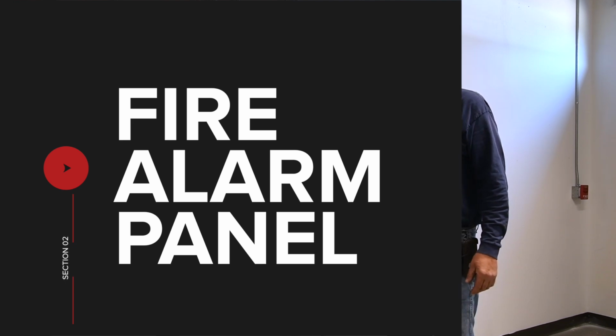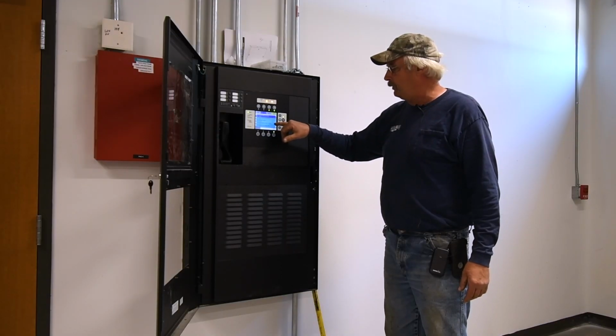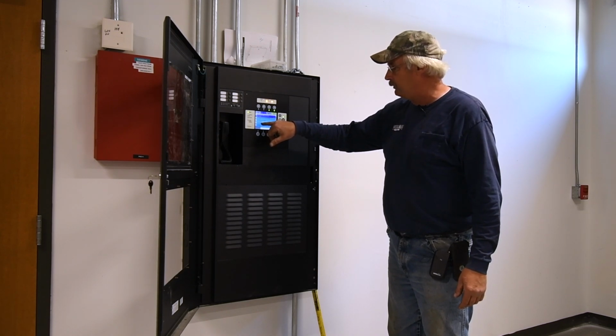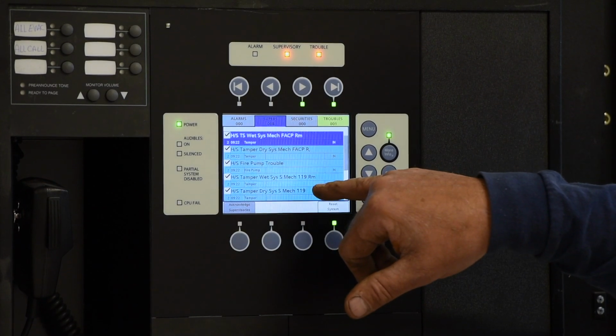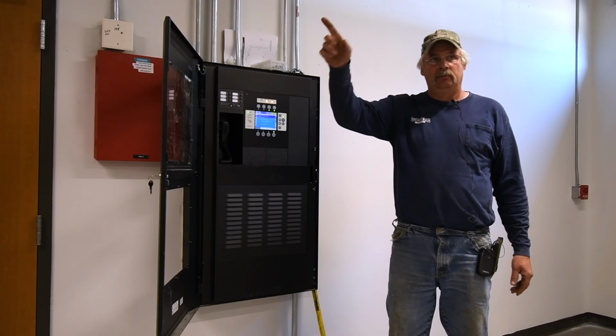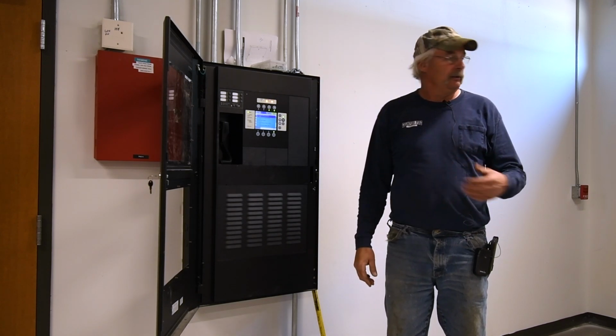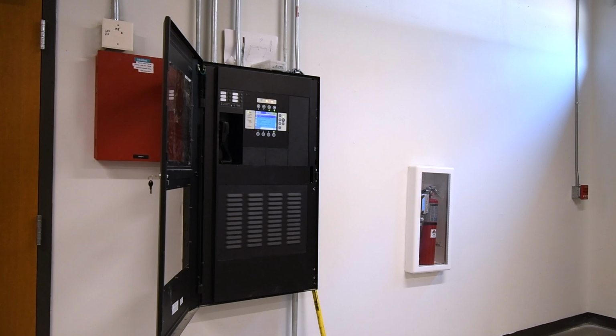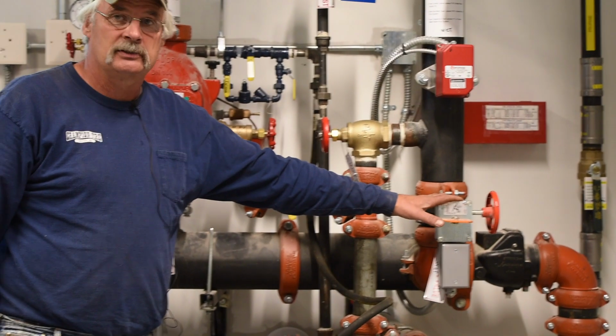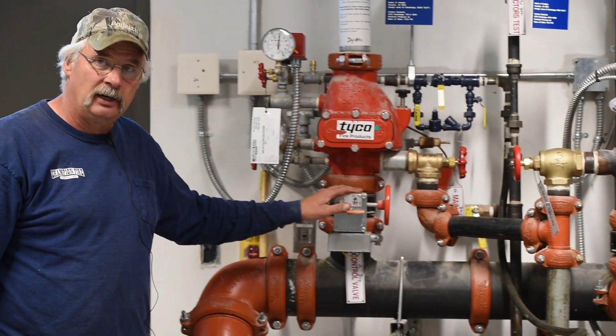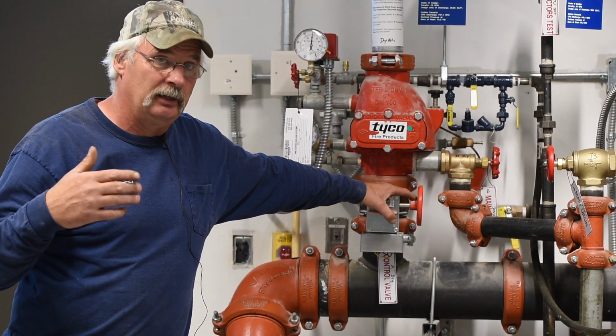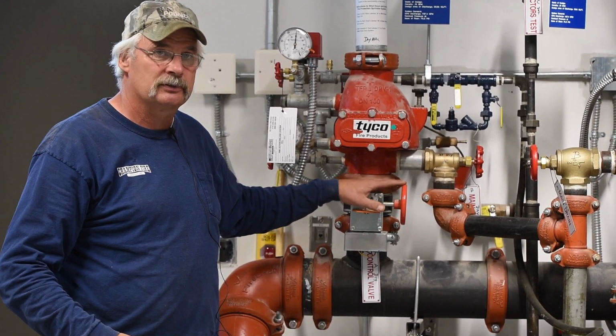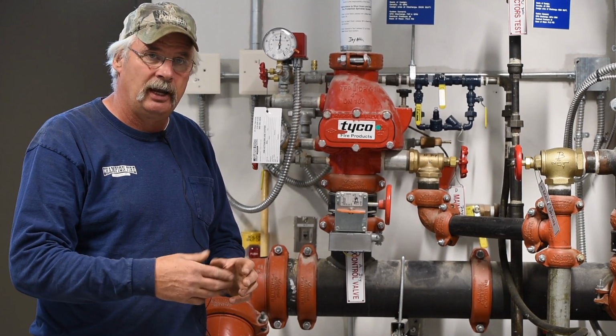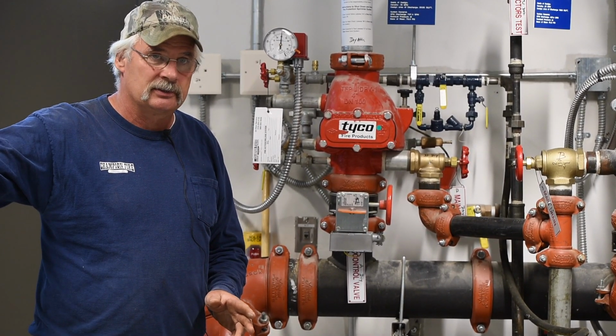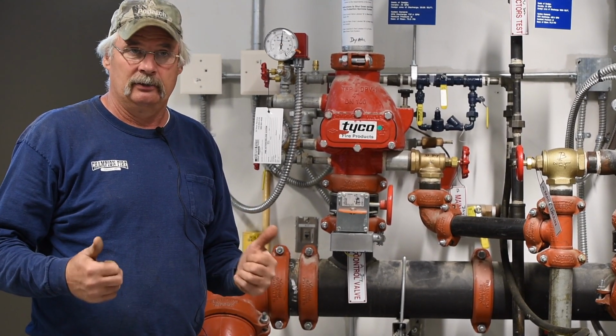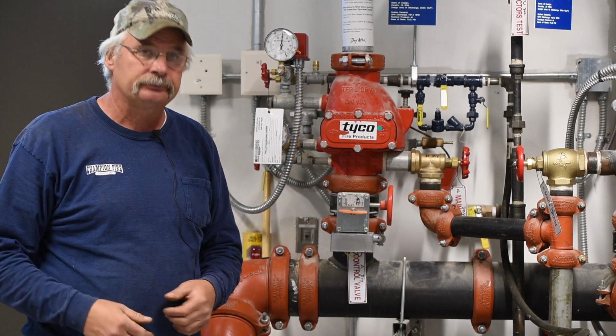In the fire alarm panel itself, if someone shuts a control valve off on the wet system, it'll say high school, tamper, wet system, mechanical room 119. And that would be the south mechanical. The north mechanical, if someone shuts one of the control valves off here, that feeds the wet system, or here, which feeds the dry system, it'll also pick it up and tell you the high school. This is a tamper switch. So if somebody turns that valve more than a turn and a half, it breaks the contacts, sends a signal to the panel, immediately puts the panel into alarm, which notifies the school.